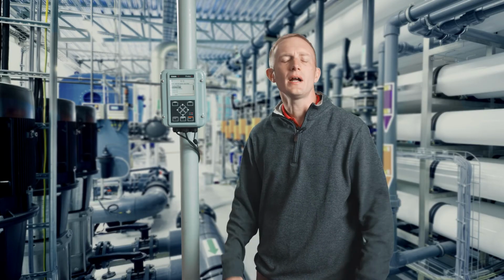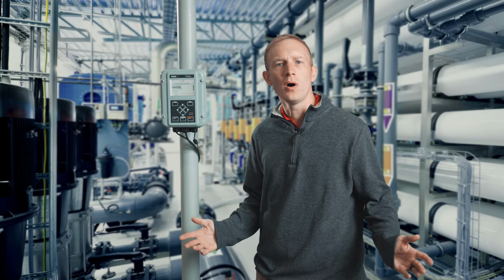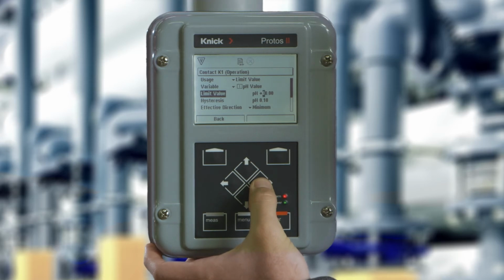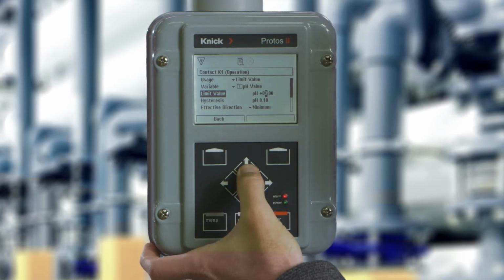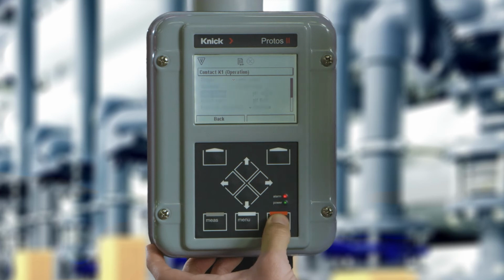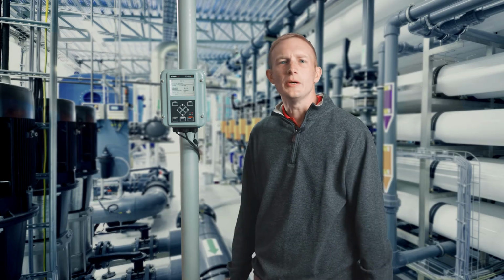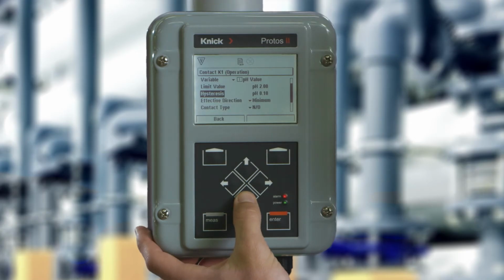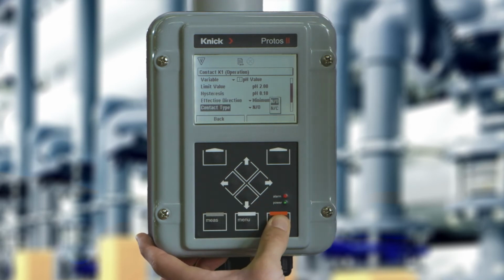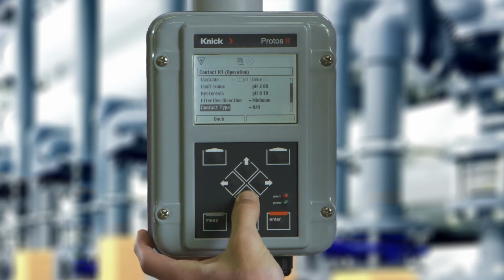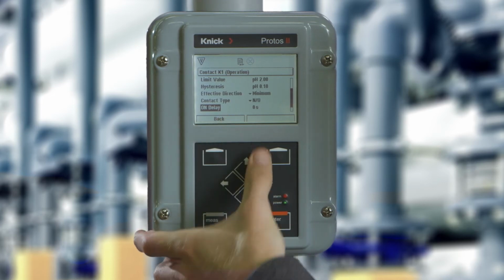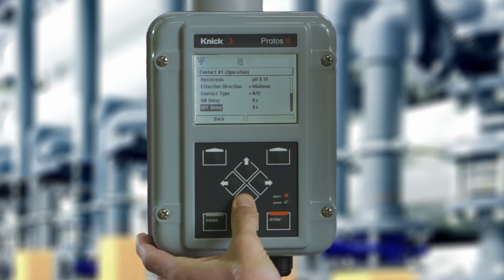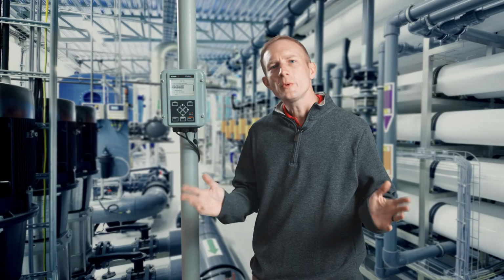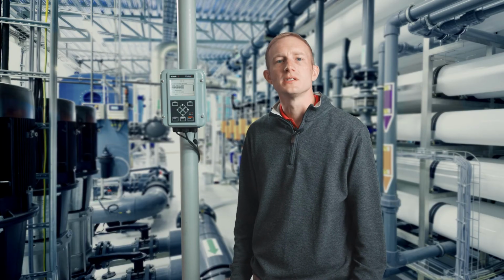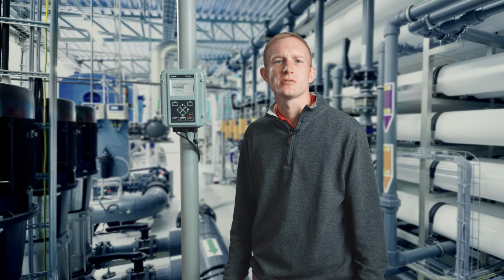Next, we can now set up our relay contact K1 for a low limit value of 2.00 pH. As you can see, we can define the hysteresis, the normal state of the contact, as well as any on-off timing delays for the relay. Once we have configured our inputs and outputs, we can now move on to our sensor selection.